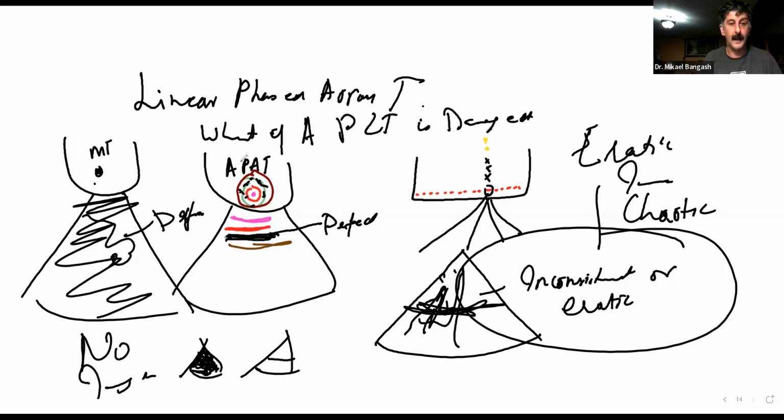In your annular phased array transducer, we see a defect across the screen like this, or more of a horizontal defect across the screen at a depth. So that means it's easier to say it's most likely this PZT that was damaged. Did that make sense? Yes.